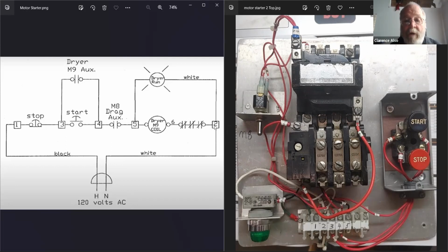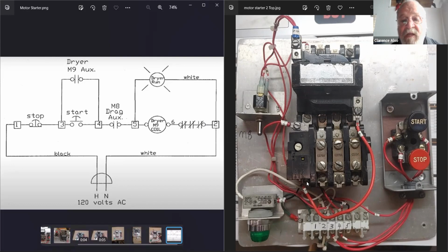So I'm going to check at number 2 with my meter. What am I expecting there? 0. And if it says 0 — and in this scenario it does say 0 — you had 0 right here on the 2 side of the overload, that's their terminal number 2. So you had 0 here but 120 there.